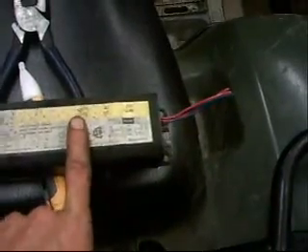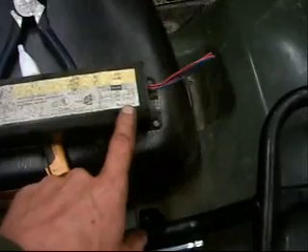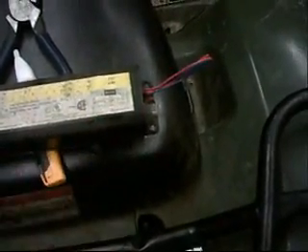There may be a little bit of difference in color. If you do replace it with a T12 ballast, you want to make sure that you get the proper voltage, which in this case is 120 volts, and you want to get one that's rated for two lamps and one that's for T12s. And even if you forget how to do this, there's a simple wiring diagram on it. There are two blue wires that go to one socket, two red wires that go to the other socket, two yellow wires on the common end, and the two white wires just jump from one socket to the other.